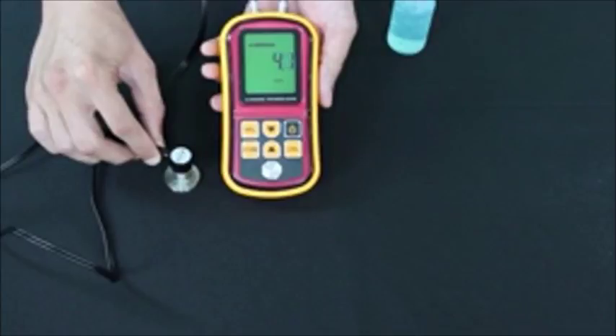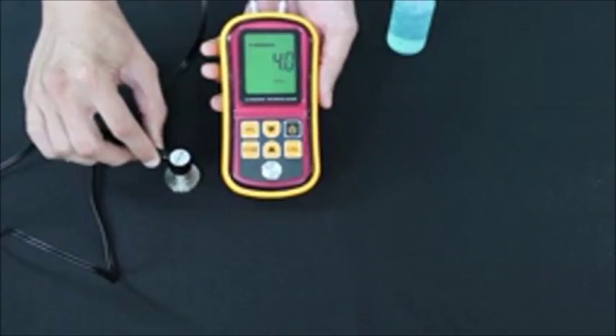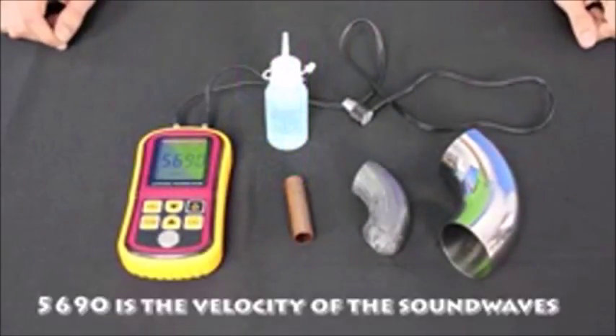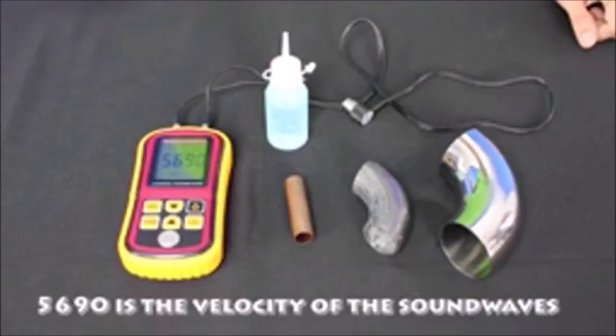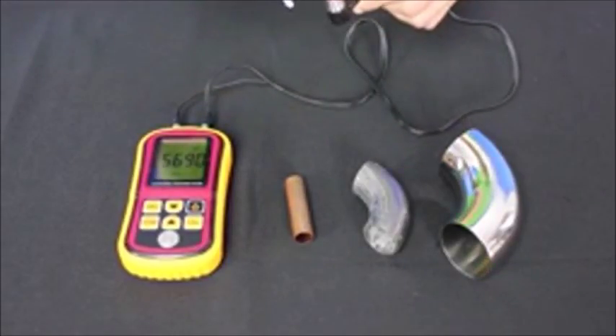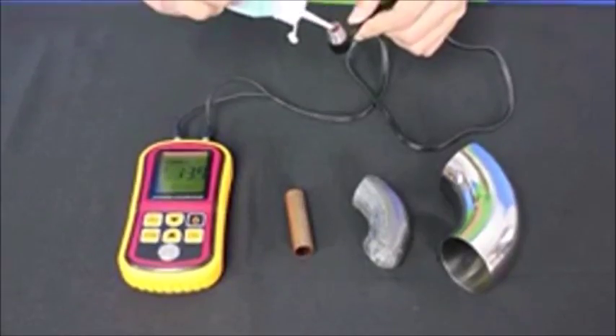Next thing you want to do is get your calibration chip and put the sensor head on the chip. This chip measures 4mm thick, so once the calibration tool reads 4mm we know that we have calibrated the thickness gauge.